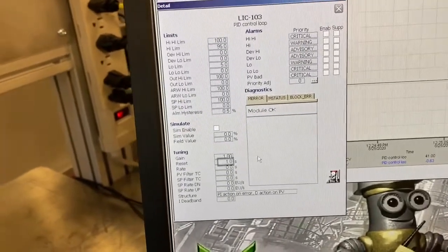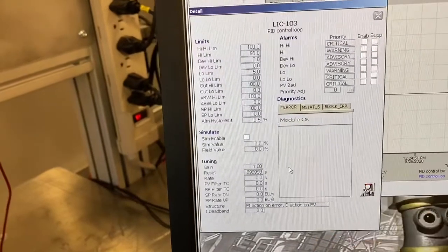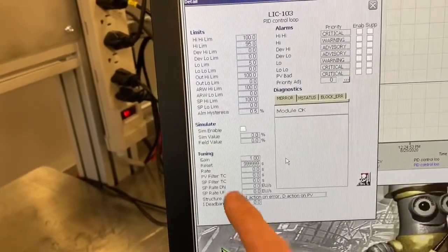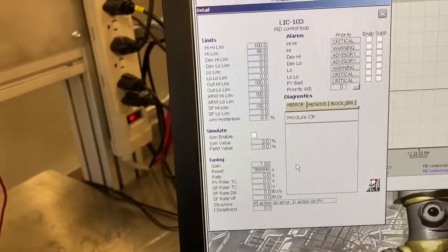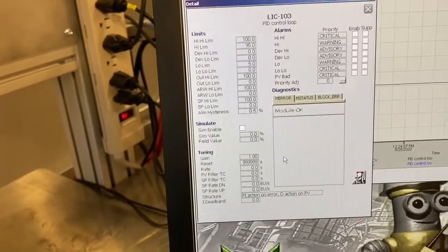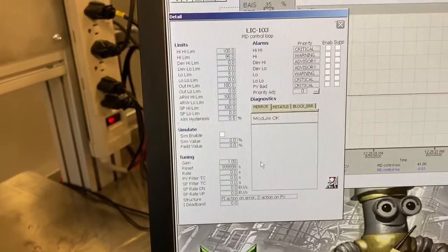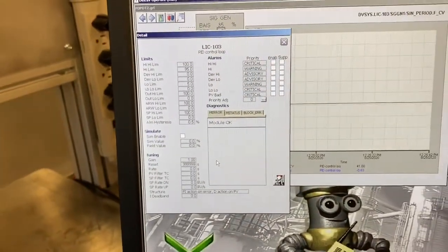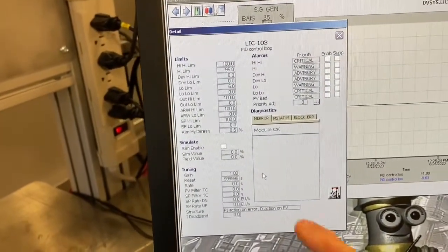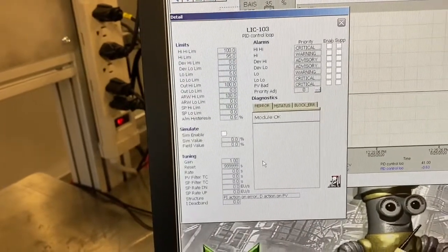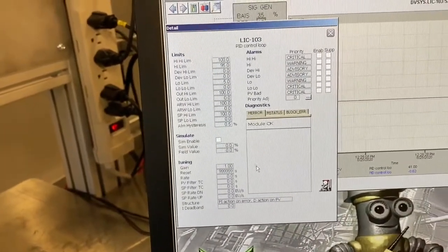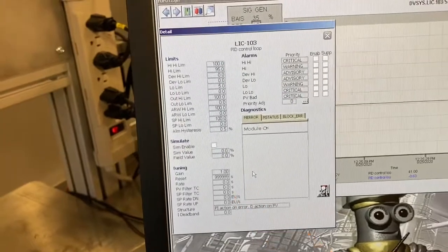This is where I'm going to key in my gain and reset value that we calculate, the KP or the proportional gain, and then the TI or the reset value. We're going to calculate those and key them in. I'm going to let you figure those out on your own, and then I'm going to key the values in here, and we're going to see how the process responds to a set point change when we use the Lambda tune.